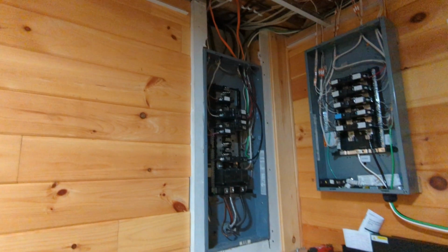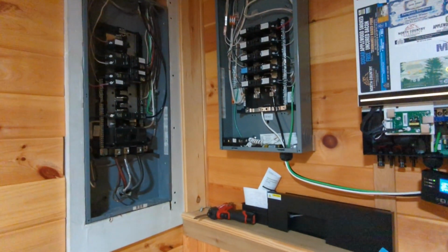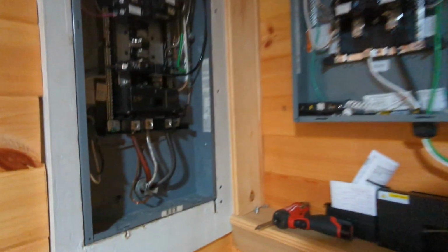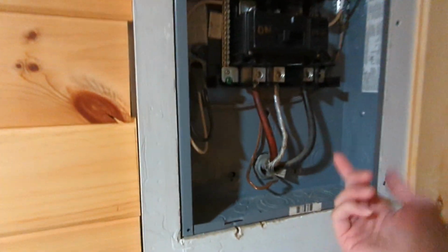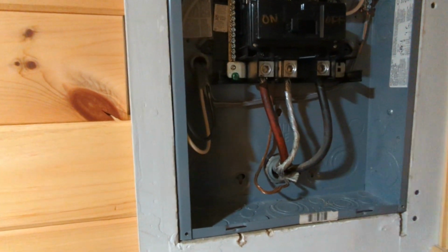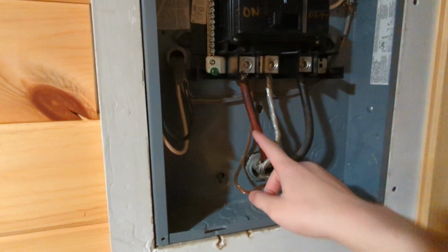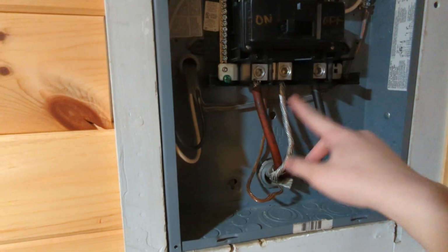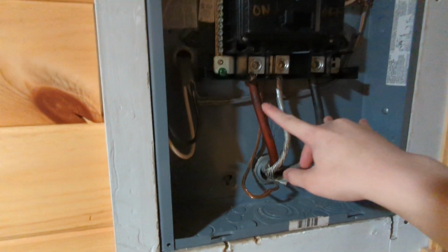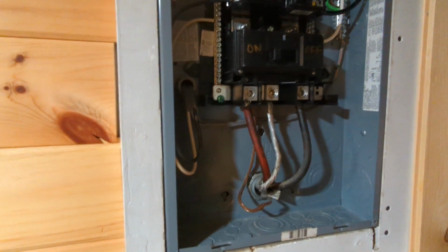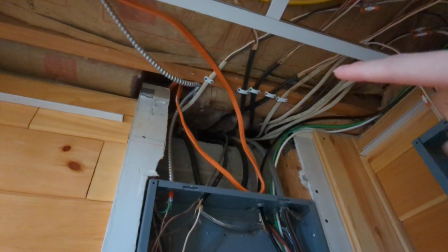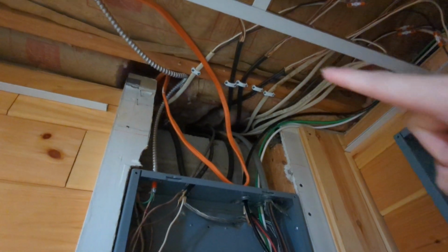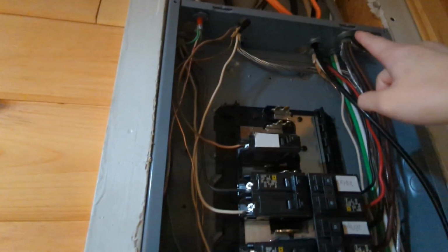I should talk a little bit about how the wiring was originally set up prior to making all the changes. I have my main service wires coming in from the street outside, passing through the power meter, and it's these 3 wires right here, or rather the 2 wires, line 1 and line 2. Between the two, of course, it's 240 volts, and then those cables up there that are pinned on the 2x6 rafter, they used to go directly through the top of this box, held in place, and they would connect into individual breakers.